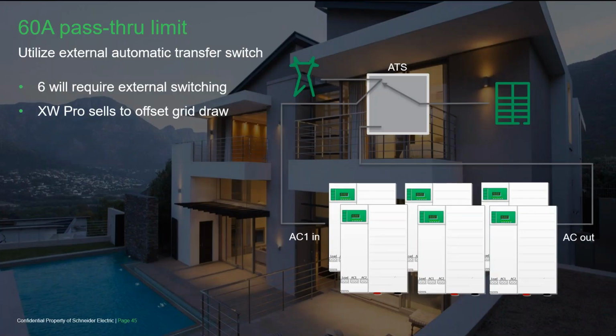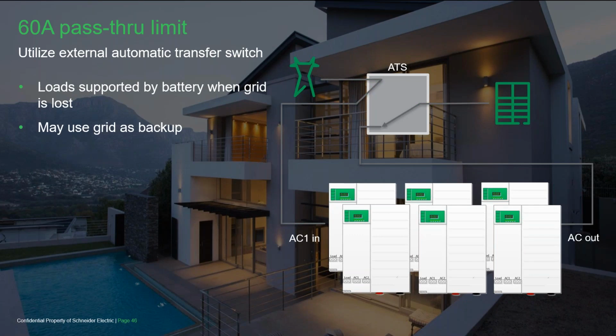Since you shouldn't pass through more than 60 amps with a multi-unit system, utilizing an external transfer switch will allow the solar power to offset the grid demand and then switch the load to the output side of the inverter in a grid outage. Here's normal operation. And here we see the loss of grid shifts all the load to the output side of the XW Pro system.